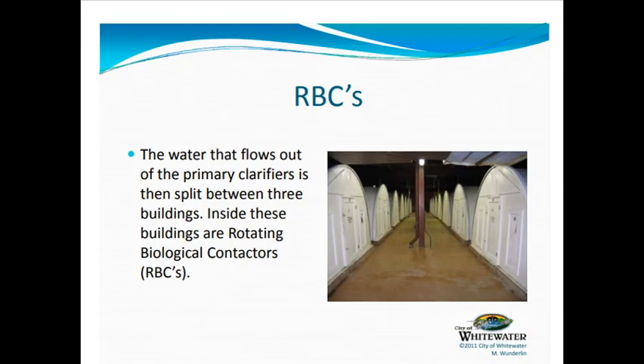After that, the water goes through what are called rotating biological contactors. You can think of these like the fish filters you see spinning in an aquarium, but they're giant — huge things. They have bacteria coating them, and that sucks up a lot of the nutrients. Not all of the nutrients, but a decent amount of the nutrients and organic matter will be taken out.